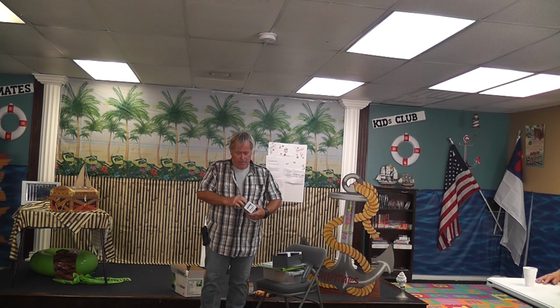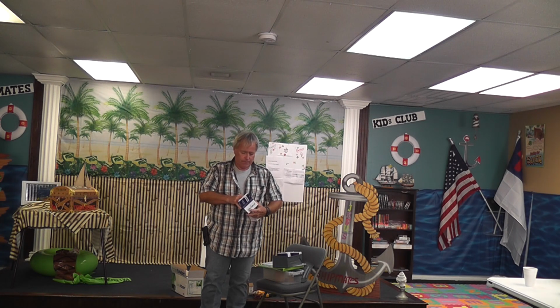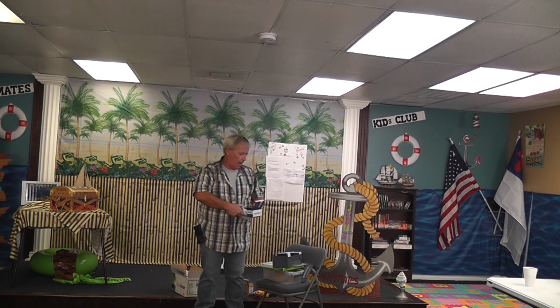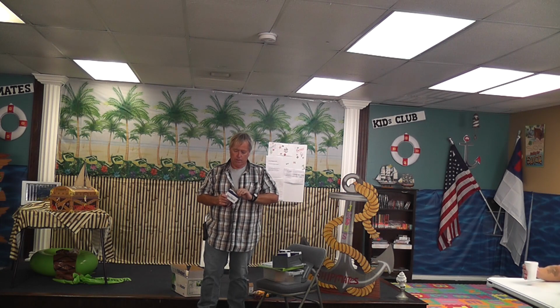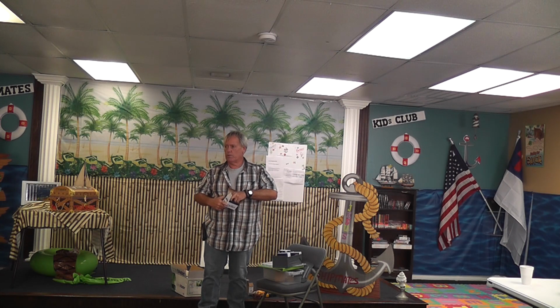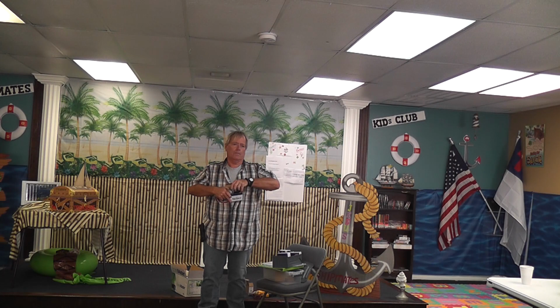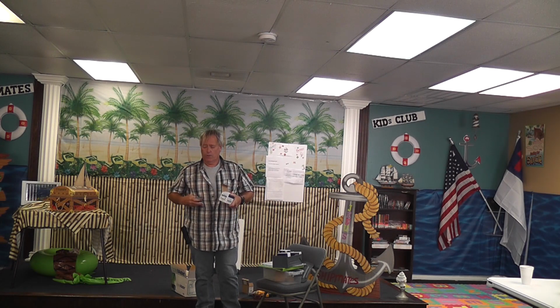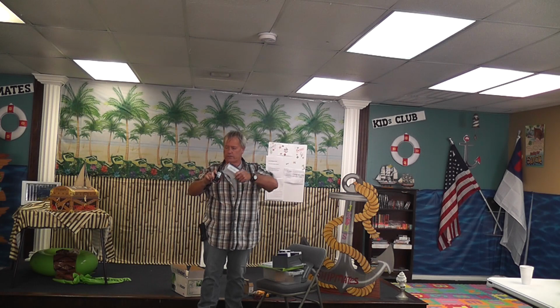There are multi-tap transformers and different VA, which is volt times amps, for the power that it's going to use. Be careful you put the right one in. You can step it up to a higher VA transformer, just re-fuse it, because 40 VA takes a 3.5 amp fuse. Or you can see the smoke rolling out as it melts. No joke. If your machine came with a 40, that's what ultimately you want to put back.